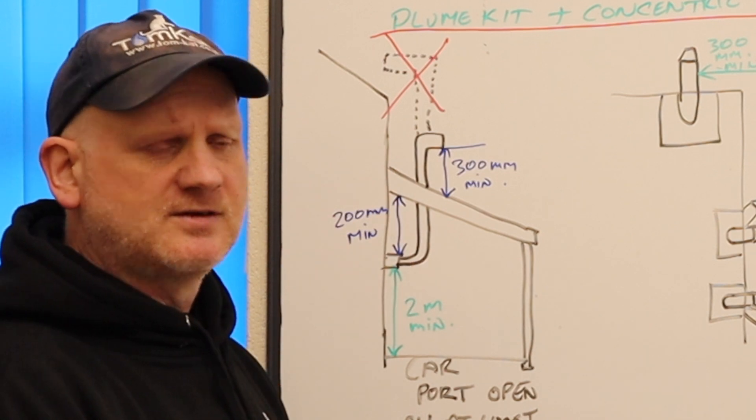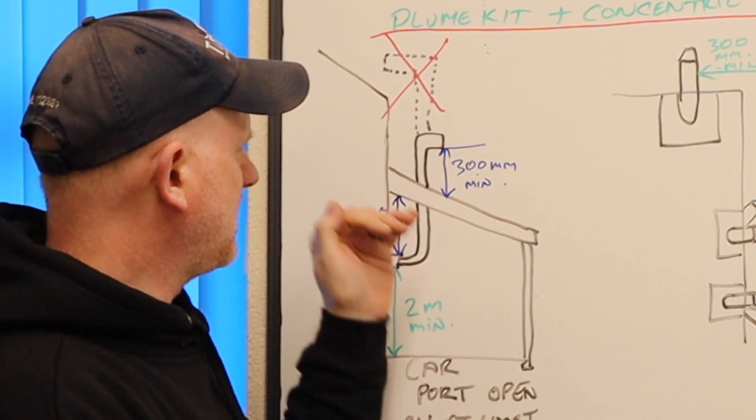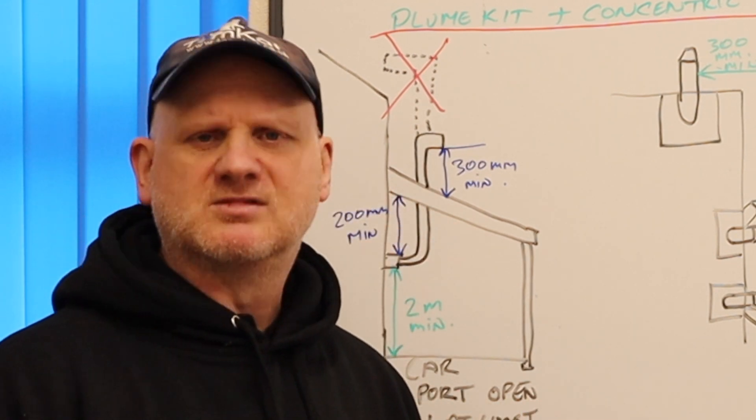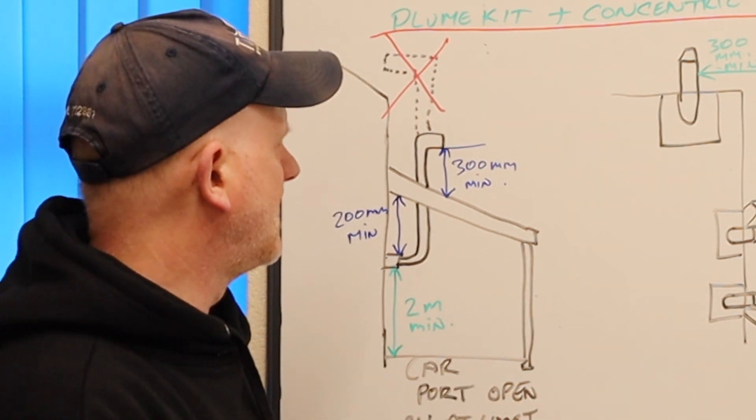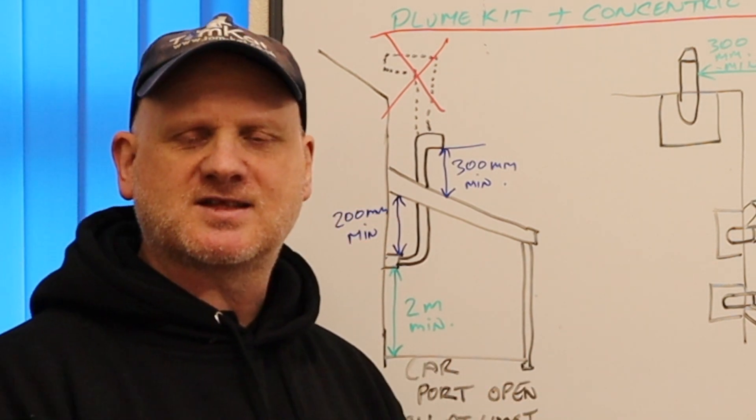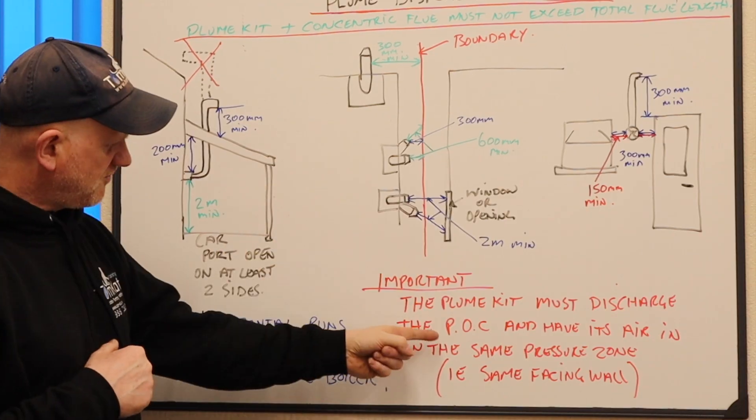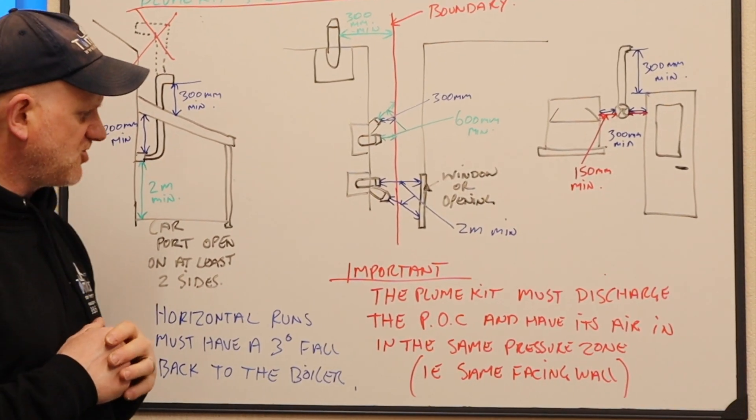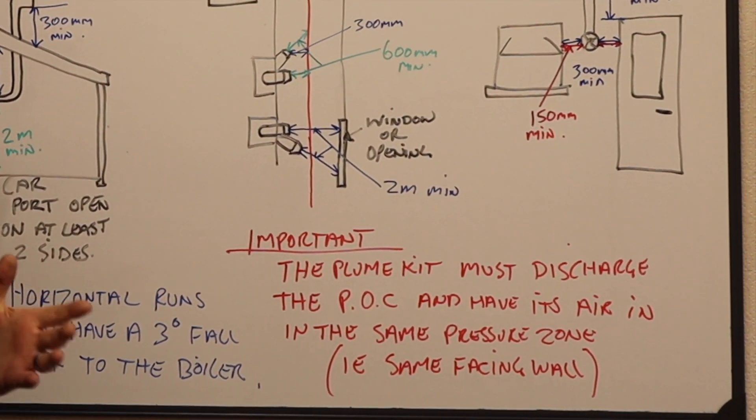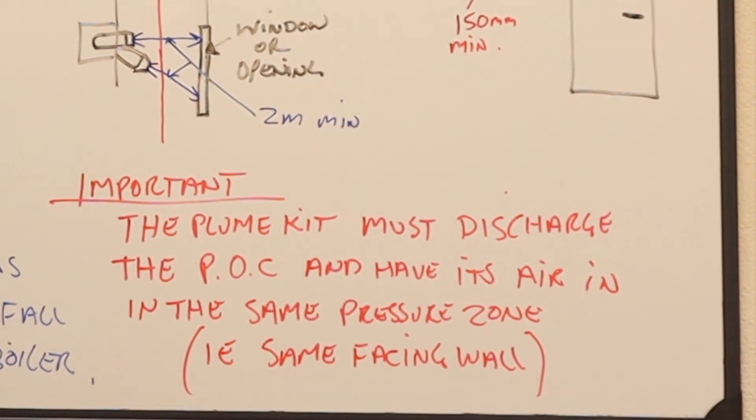So when we come above the roof, we must be 300 above the pitch of the roof like we would be from ground level to stop snow and leaves and rain bouncing back in there. The other major thing is it has to face the same way as the air inlet because, like I've put here, the plume kit must discharge its products of combustion and have its air in in the same pressure zone. That basically means facing the same way on the wall.